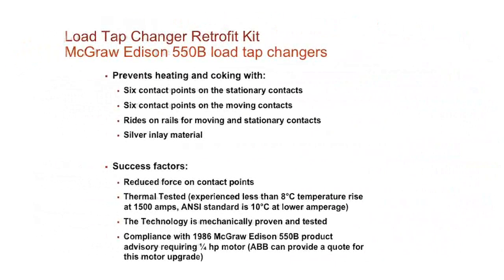It prevents the heating and coking, because we have the 6 contact points going on and off. They're moving contacts as well. They're spring-loaded inside there, so they have tension on them themselves. Even though they're current carrying capacities, that's where we get our tension. They ride on the rails. We have the silver inlay that I pointed out.